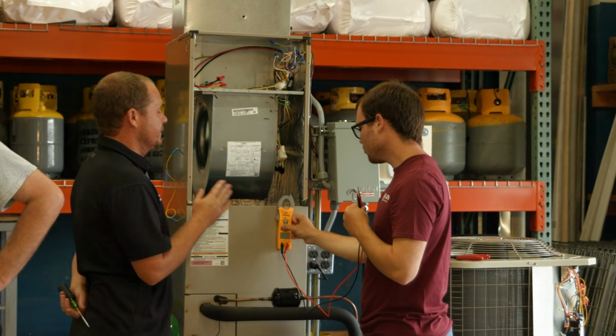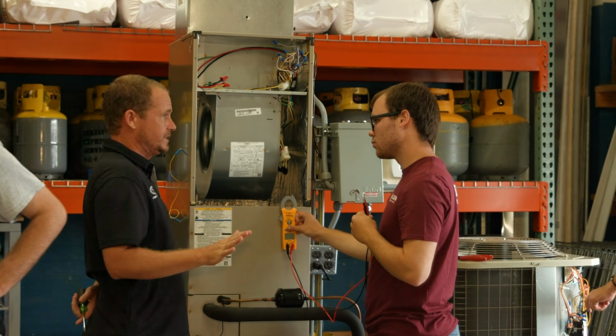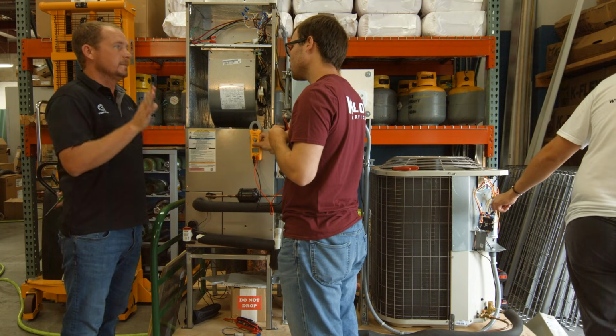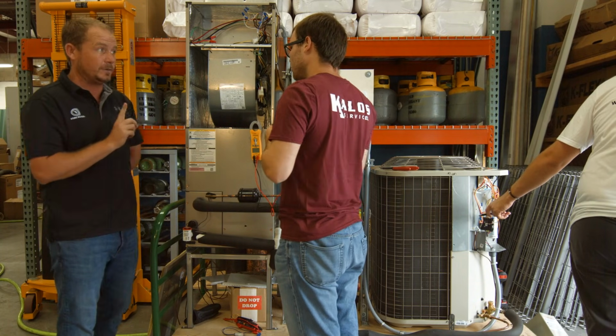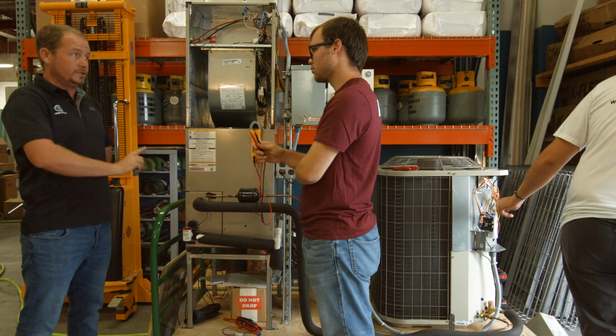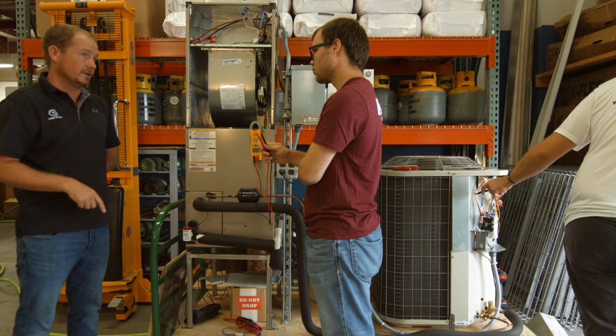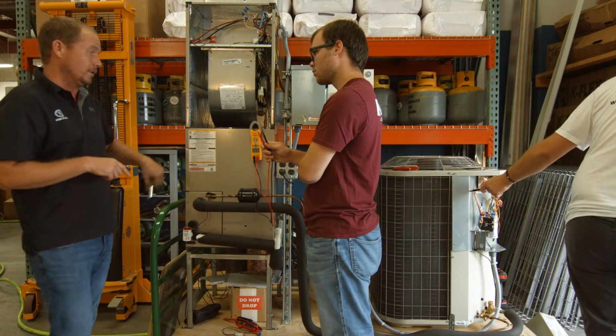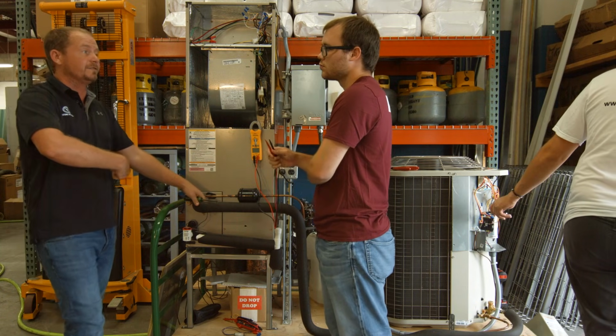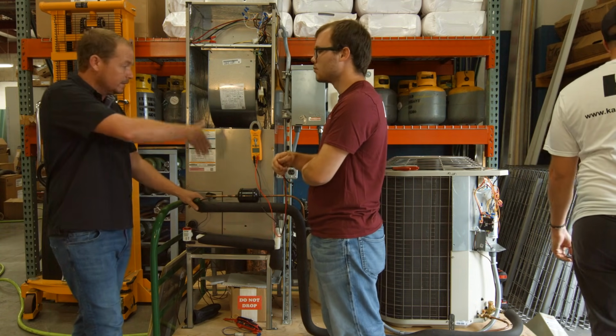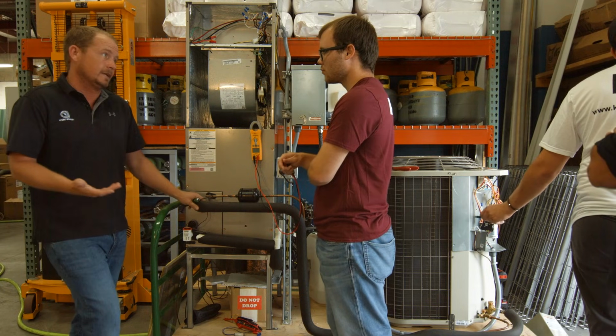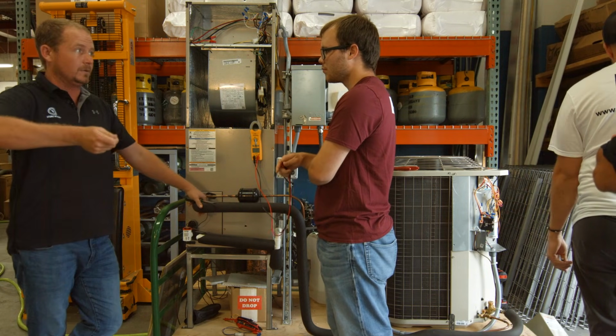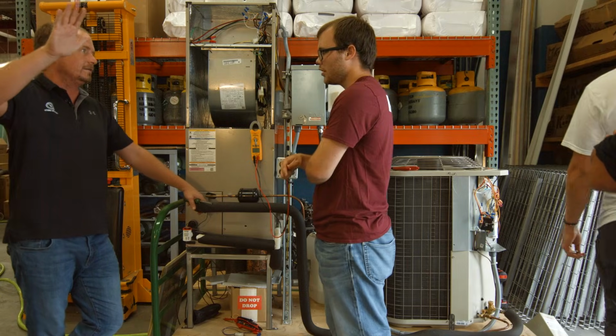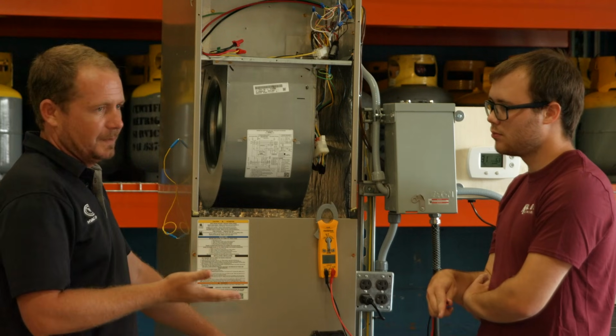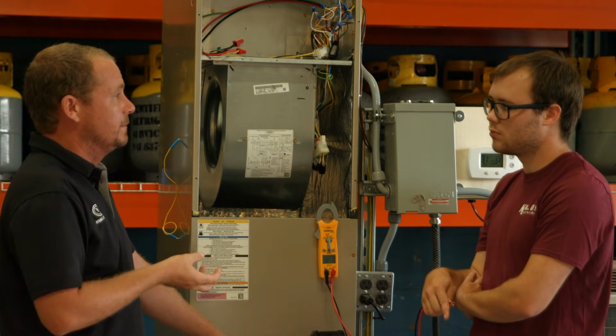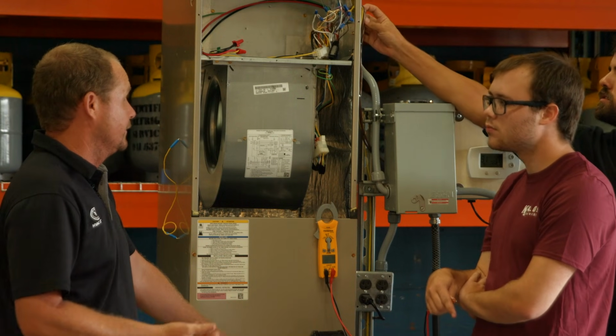Now let's go ahead and confirm that with an ohm test. Normally this is where you'd stop. You don't need to do any more at this point, but let's do it with an ohm test. Actually, quick caveat: at this point you would want to dig back, because we have these underground thermostat wires. You'd want to dig back and see if you could find where the break is, anywhere that you can visually see, because that's going to be most common. Somebody weed whacks it, whatever. Don't immediately jump to, you need a new wire. Old bad splice they did. Old bad splice, exactly. Or sometimes people will splice some conductors and they won't splice them all. That's another common mistake.